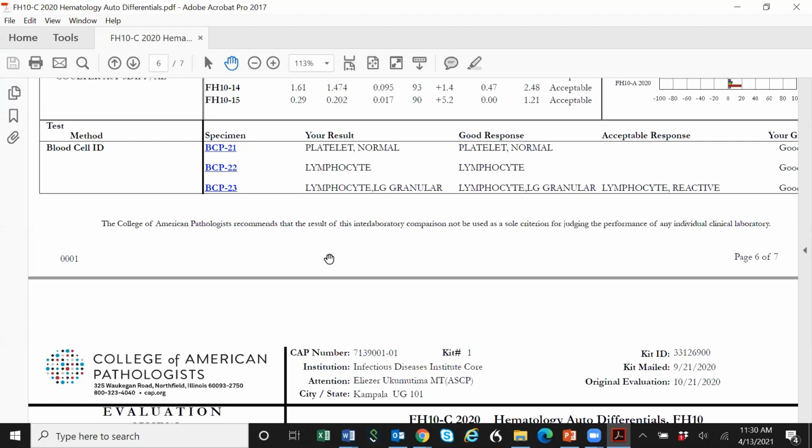Their accrediting body wants them to provide justification on the frequency of participation in PT schemes. Is there a recommended frequency, or does it depend on the analyte and the provider? It depends on the provider, but most of them are the same. If you're running a lab, you should be enrolled in PT at all times. It's part of basic practice, I would say. Once you enroll, most PT schemes, whether from the US, Australia, Africa, wherever, usually send no less than 2 challenges a year, and usually no more than about 4. So it's usually 2, 3, or 4 per year. Actually, no, I take that back. The most I've seen is 6.